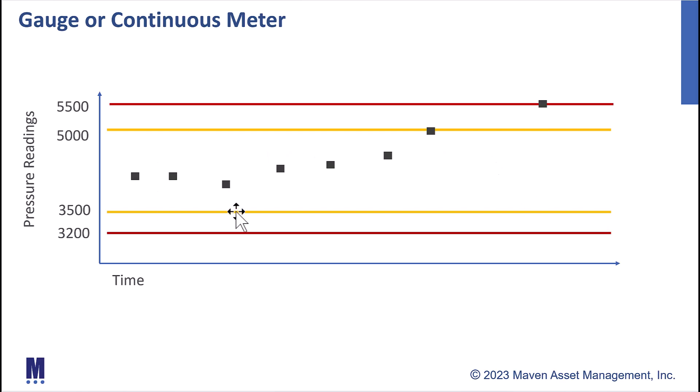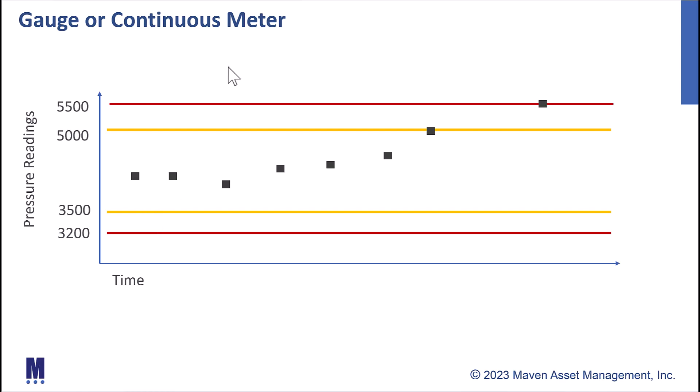According to the specifications for this particular centrifugal pump, this is the area of meter readings that we want to be in. We want to be between 3,500 and 5,000 PSI. If we go above or below those values, we can potentially be having a problem with our asset. And then if we exceed those, the action limit, so if we exceed 5,500 or go below 3,200, we want to take action on the asset, inspect it, see what's going on, so an asset failure doesn't occur.